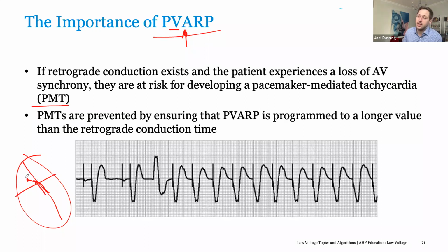So with a PMT, what can actually happen here is an atrial event is sensed. The device senses it, it paces in the ventricle. But because the atrium may be in refractory for whatever reason, or say this is a PVC, the electrical impulse runs retrograde into the atrium. It is sensed again. The device sees it, interprets it as a true atrial event, and then paces again in the ventricle. And this creates essentially an endless loop tachycardia, but with the pacemaker being the accessory pathway.